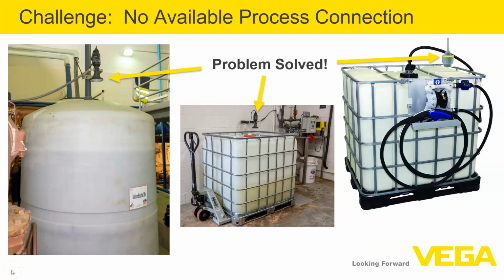Radar signals penetrate non-conductive products like plastic and fiberglass. The radar signal essentially ignores the vessel structure and gets a reflection off the material inside the tank to determine the level. This allows us to mount the radar above the tank to easily measure level without the need for a process connection or to penetrate the vessel in order to take a measurement, like in the case of the tote or plastic drum. We can even measure through double-walled plastic and fiberglass tanks.